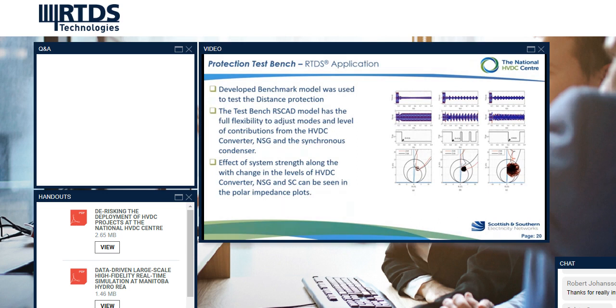As the system strength reduces and the level of contribution from the HVDC converter, synchronous condenser, and the non-synchronous generation is changed, the behavior of the impedance of the system during the fault changes widely. This can be seen in the polar impedance plot at the bottom of the picture.